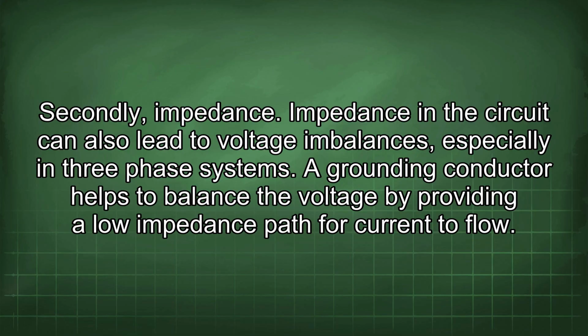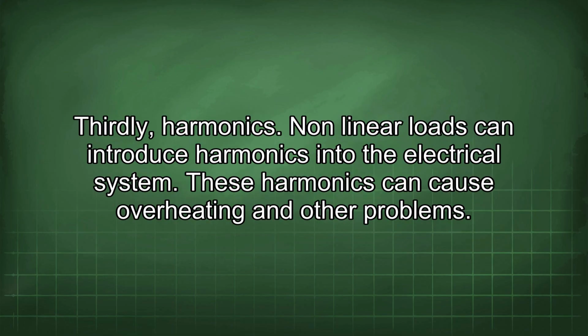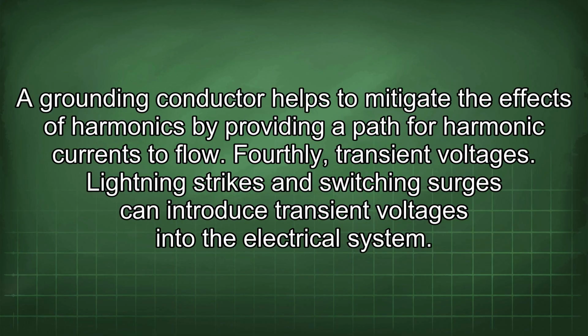Impedance in the circuit can also lead to voltage imbalances, especially in three-phase systems. A grounding conductor helps to balance the voltage by providing a low impedance path for current to flow. Thirdly, harmonics. Nonlinear loads can introduce harmonics into the electrical system. These harmonics can cause overheating and other problems. A grounding conductor helps to mitigate the effects of harmonics by providing a path for harmonic currents to flow.